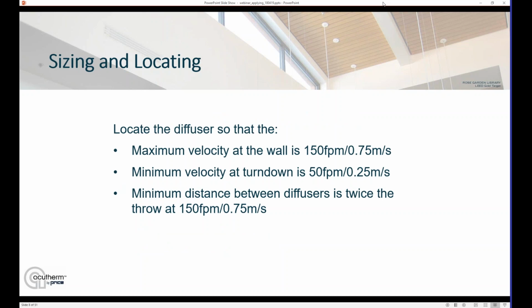Now, with any diffuser, you want to make sure you don't have that high velocity air hitting the occupants. So we recommend that the maximum velocity at any wall is the throw distance for that 150 feet per minute throw. However, you want to make sure you can maintain good room air movement when the system turns down. It is a VAV system after all. So it's also nice to place the diffuser where at turn down the 50 feet per minute throw distance reaches to the wall. And if you're working in a larger room, halfway between the diffusers, you can pretend they're walls and use those same rules, or basically double that 150 feet per minute throw distance between two diffusers.